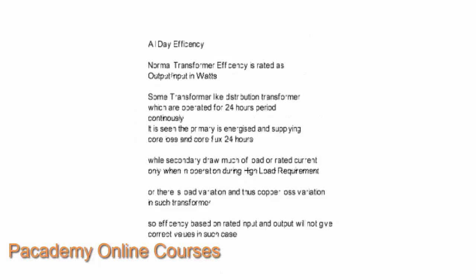Another term is all-day efficiency. Normal transformer efficiency is rated as output divided by input. But for some transformers like distribution transformers, which are operated continuously for 24 hours, the primary is excited for 24 hours and incurs core losses, while the secondary is highly loaded only during peak load times and very lightly loaded otherwise. There will be a variation in copper losses over the 24-hour period, so the standard efficiency method will not give a very accurate result.